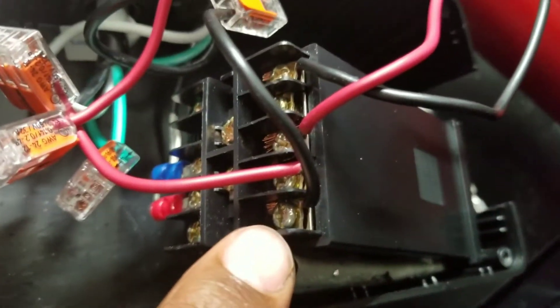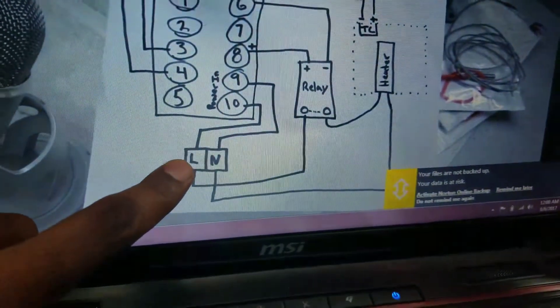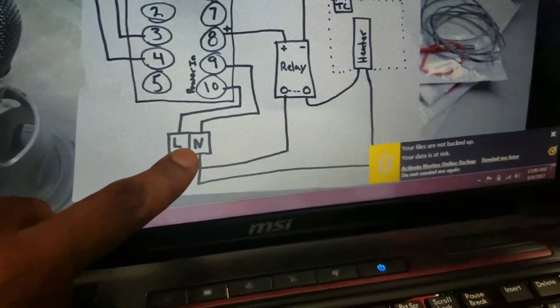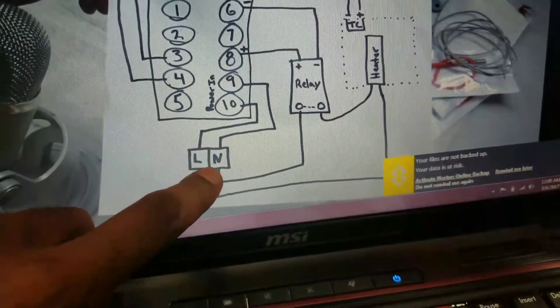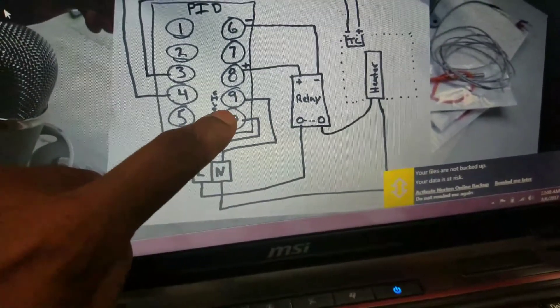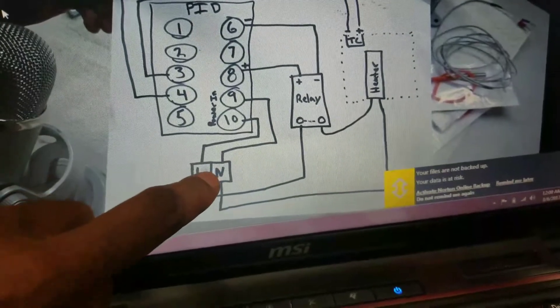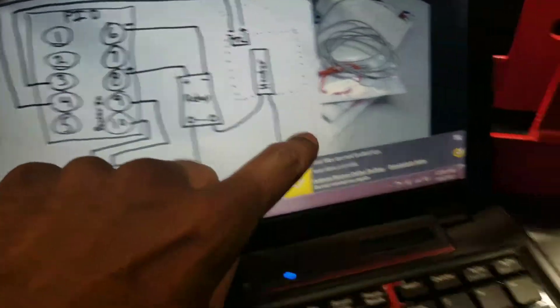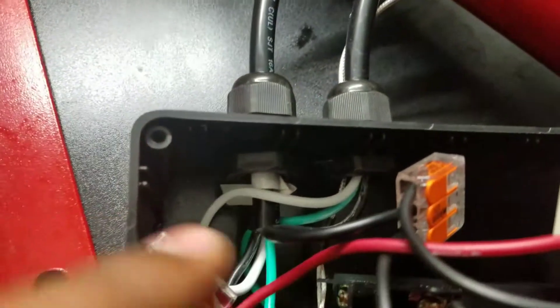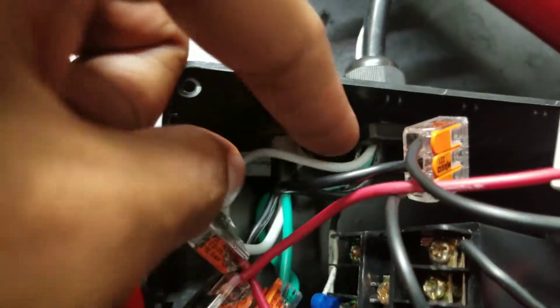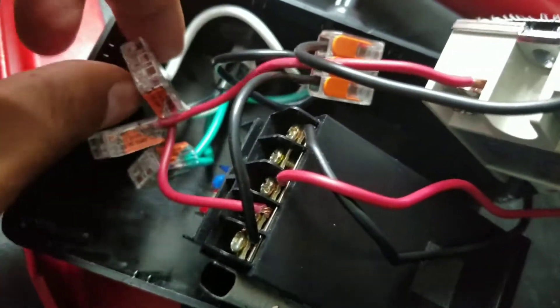Now the neutral, which will be my white cable, is going to go to a three-piece Wago and then go over to number nine on the PID and then over to the heaters. So if I come over here, find my white cable coming in, goes to a three-piece Wago.